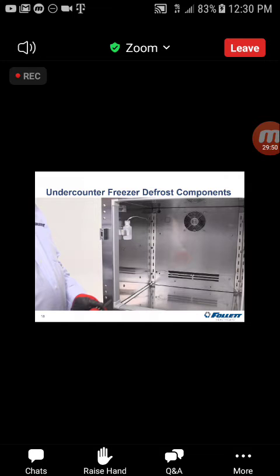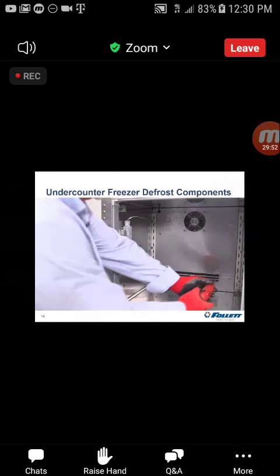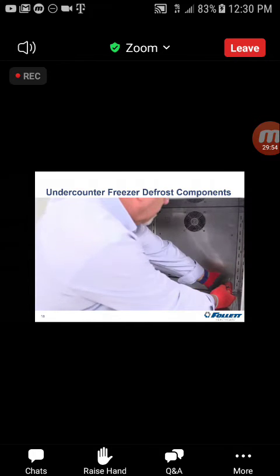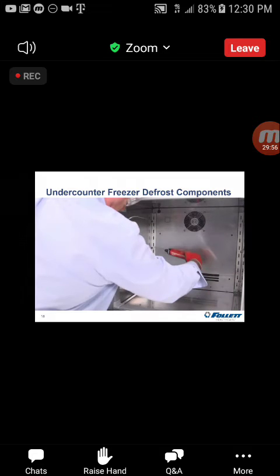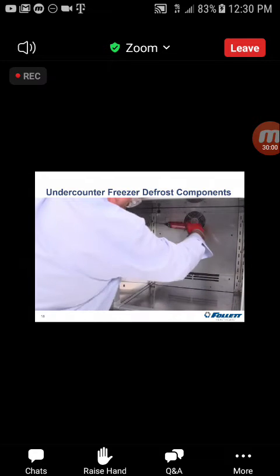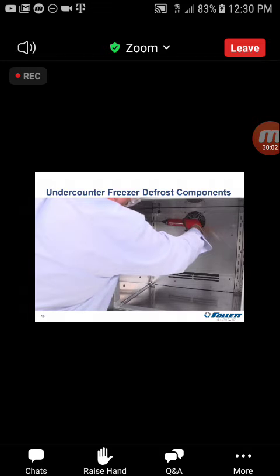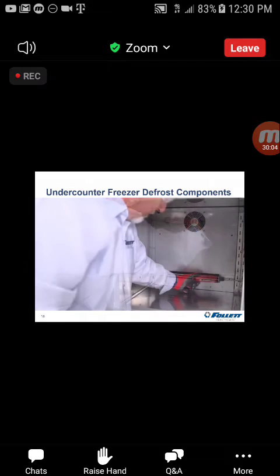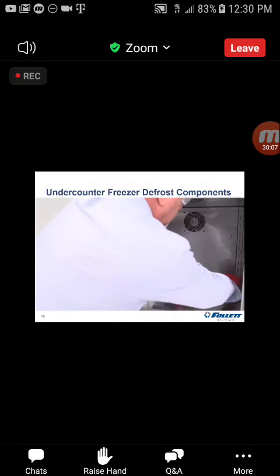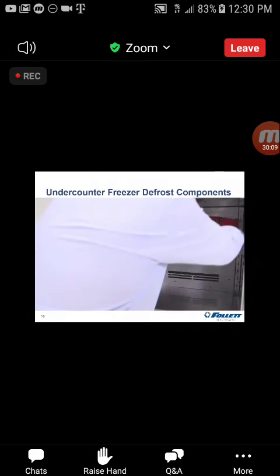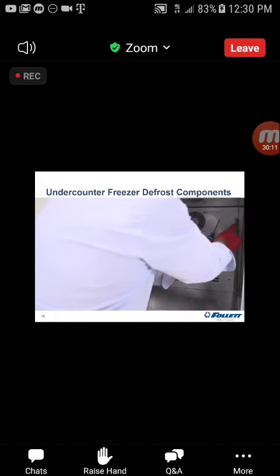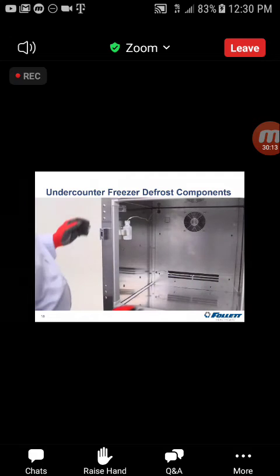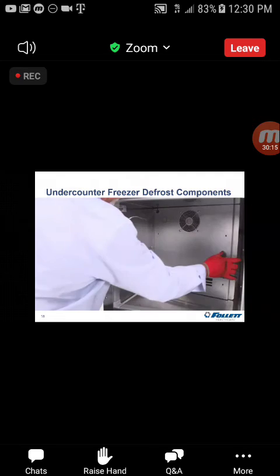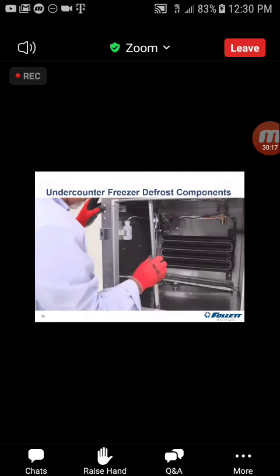On Follett under-counter refrigerators and freezers, the evaporator is located behind the rear wall panel of the unit. To access the defrost components on an under-counter freezer, first remove the 6 Phillips head screws securing the panel to the unit, and then loosen the screws on the bracket on the left. Remove the screws on the shelf bracket on the right, and then the panel can be pulled forward.